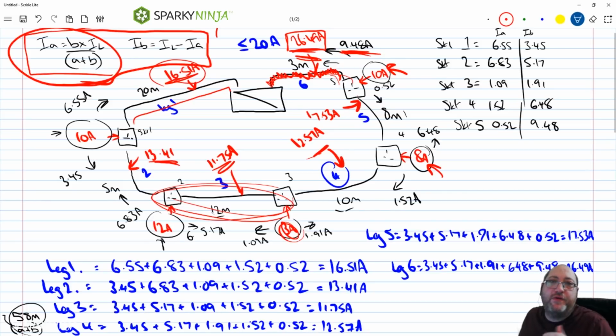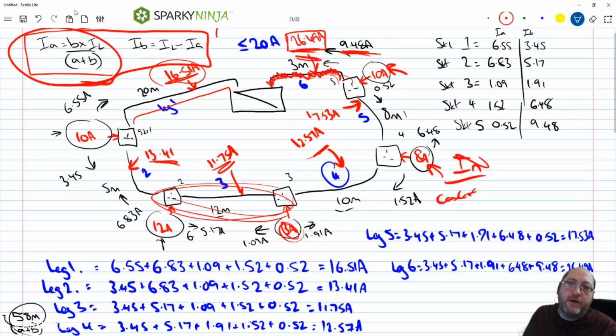But this is something that I do on the design course. Just so you know, if you're doing cable calcs with ring finals, you want to make sure that when you're coming to your IN over CA, CI, CC, CG, all that, use 20 amp. That's the value that needs to go over the rating factors when we're doing cable calculations. So do make sure that you remember that with the ring finals.